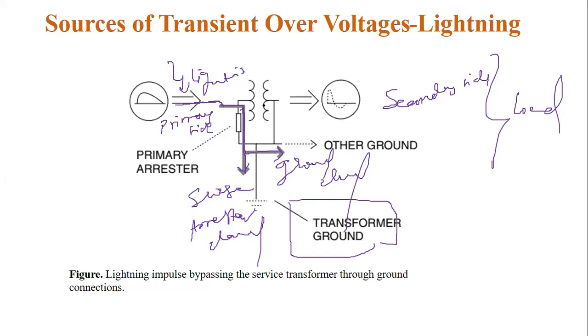So before that clearing, some amount of voltage, in kilovolts, is injected into the secondary side of the transformer also. Here the waveform is like this - I'm not saying this is a perfect waveform, but the lightning hits, and even though the surge arrestor clears it, some amount is injected, and that injected impulsive transient looks like this.